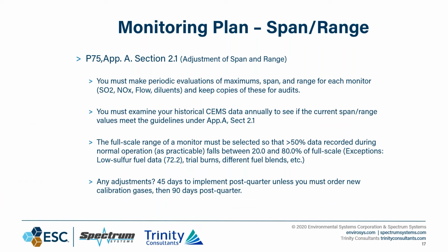Talking about span and range, you have to make periodic evaluations of your maximums, spans, and ranges for each monitor. That's for SO2, NOx, flow, and diluents, and keep copies of these for potential audits, because you never know. You have to examine your historical CEMS data annually to see if the current span or range values meet those guidelines.